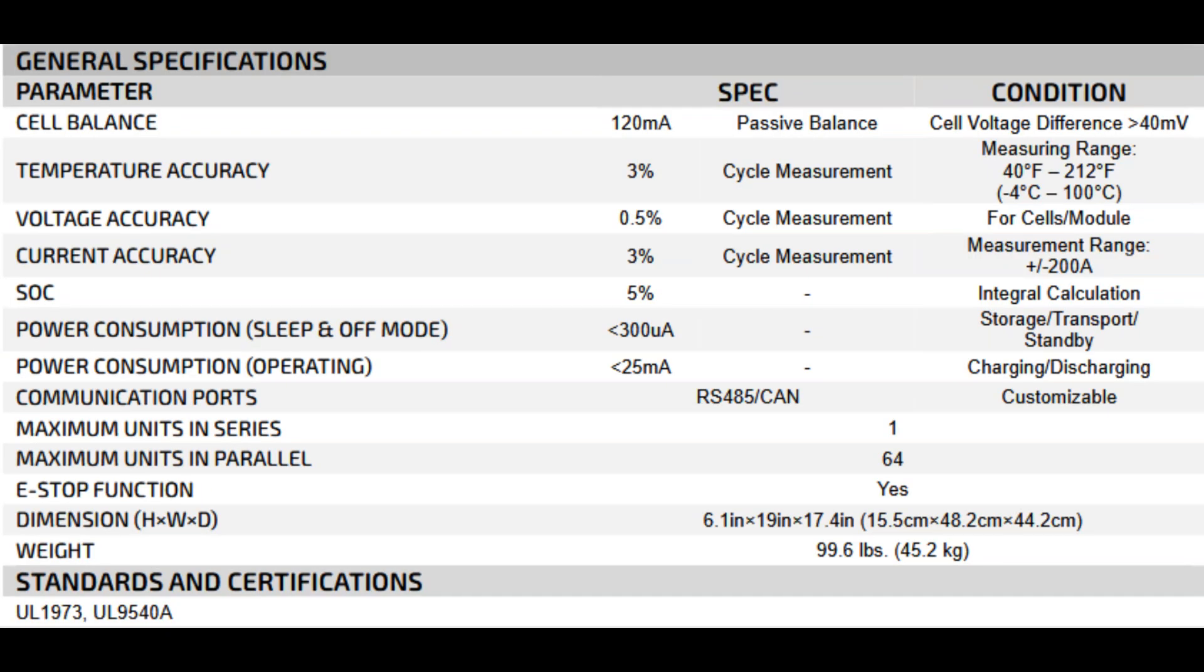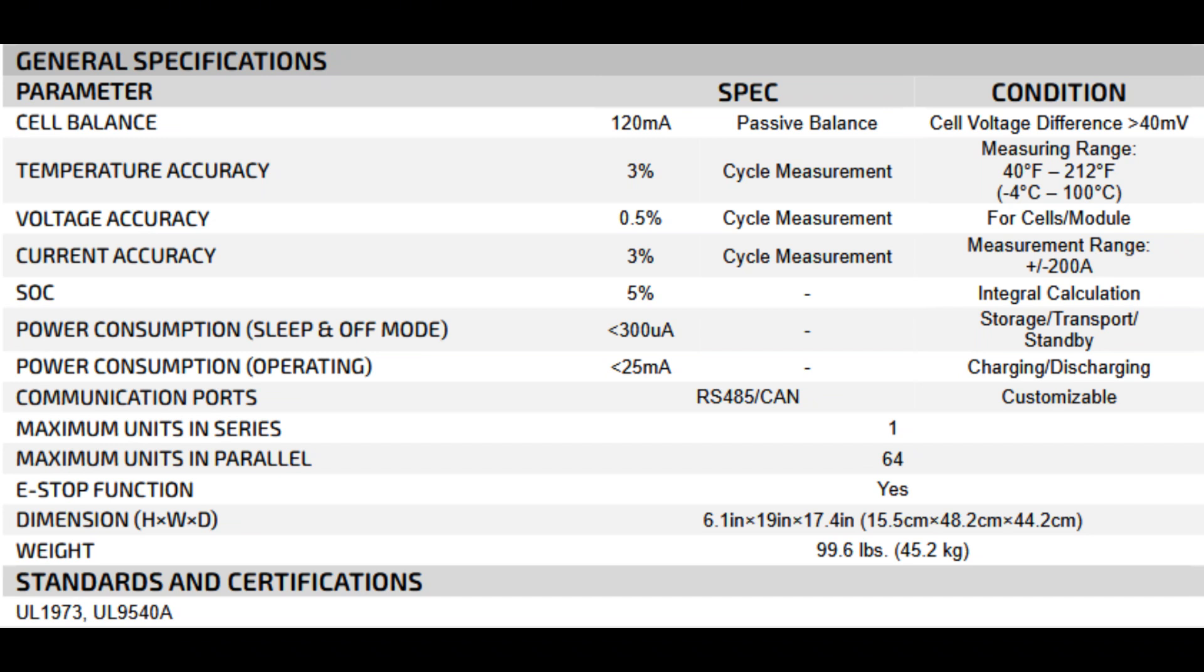The general specifications: maximum units in series one, i.e. 48 volts nominal. Maximum units in parallel 64. E-stop function yes. Dimensions 6.1 by 19 by 17.4 inches. Weight 99.6 pounds. Certifications UL-1973, UL-9540A. One in series means each pack is built to be a single 48-volt battery. Parallel up to 64 means you could theoretically reach over 300 kilowatt hours in a single battery bank. UL listings confirm these batteries meet rigorous safety standards.